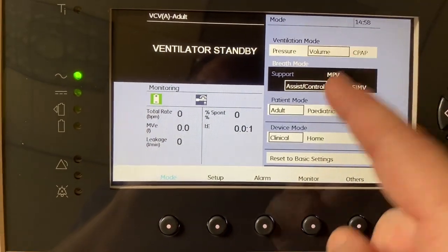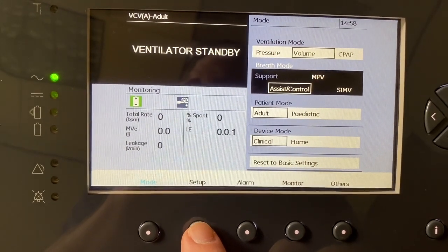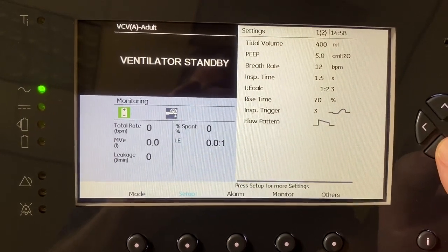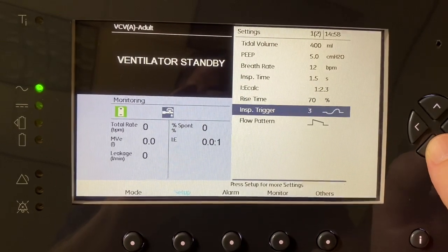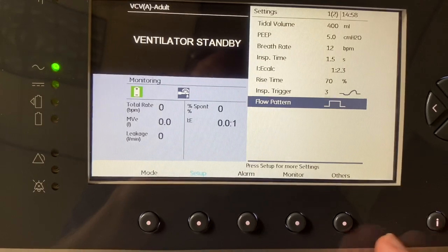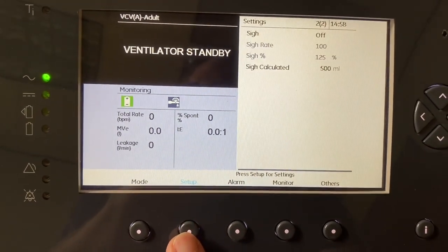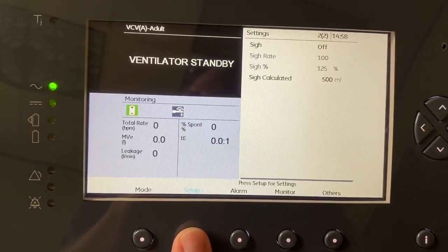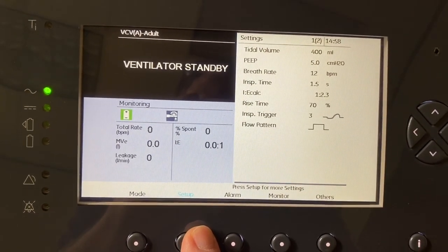I have my volume and my assist control. If I want to set certain parameters, I can click on setup. Here I can adjust my tidal volume, PEEP, breath rate, I-time, rise time, inspiratory trigger, and my flow pattern. If you press setup again, you will have more settings: Sigh, Sigh Rate, Sigh %, and Sigh Calculated. Press setup again and it takes you back to your original screen.